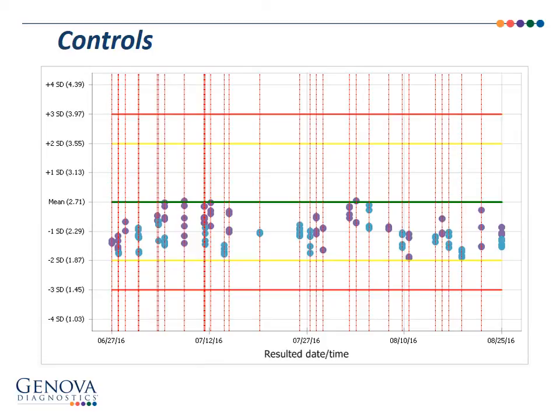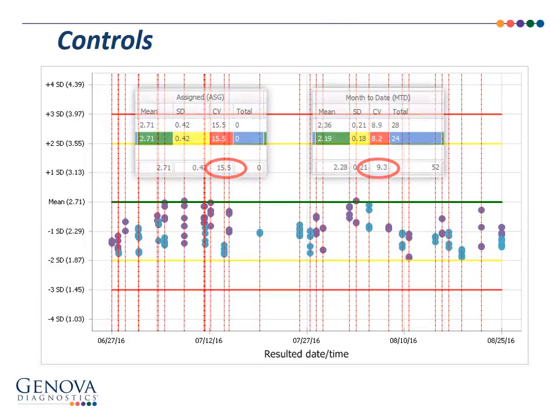In this example, you can see that our acceptable range is between the 2 yellow bars, but all of our points are falling between the mean and the bottom SD. So this is telling us that, number one, our mean is set too high, but also that our CV is set too wide. The spread is not quite what we set it. So TQC actually gives us this information.